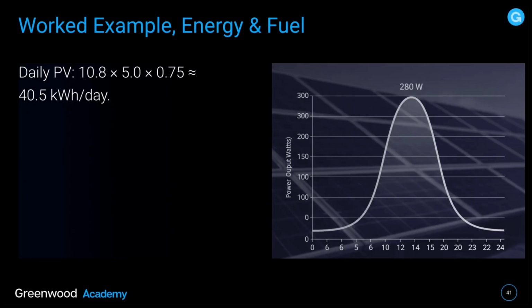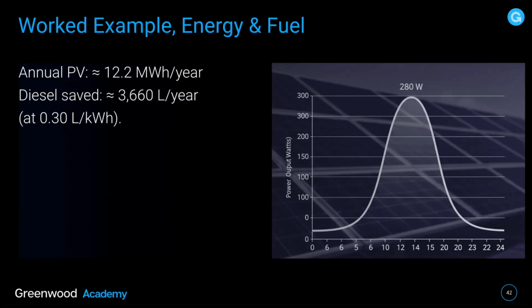Daily PV, 10.8 times 5 times 0.75. So you're looking at around about 40.5 kilowatt hours a day. That's what it's actually going to produce on average. Annual PV, approximately 12.2 megawatt hours a year. The diesel saved is 3,660 litres a year, and that's at 0.3 litres per kilowatt hour. So it's a considerable saving of diesel.